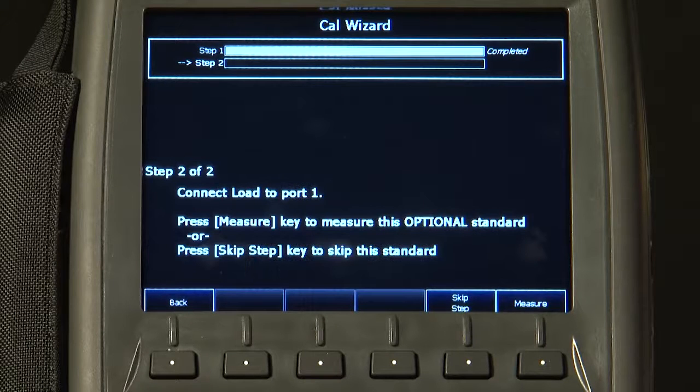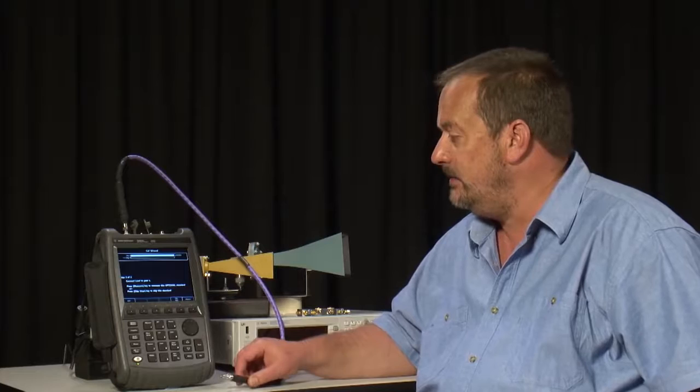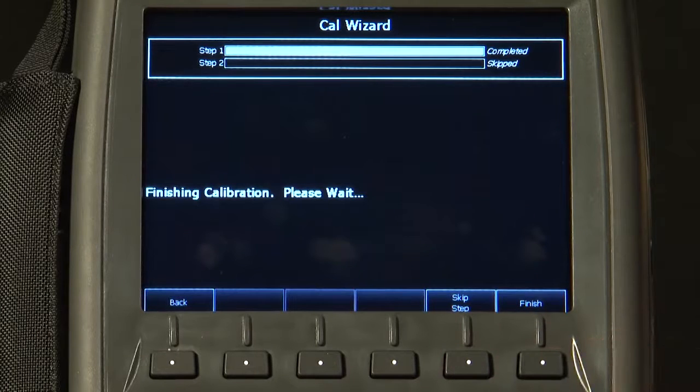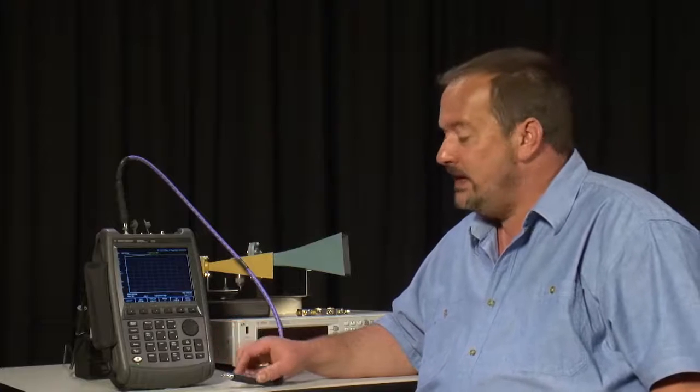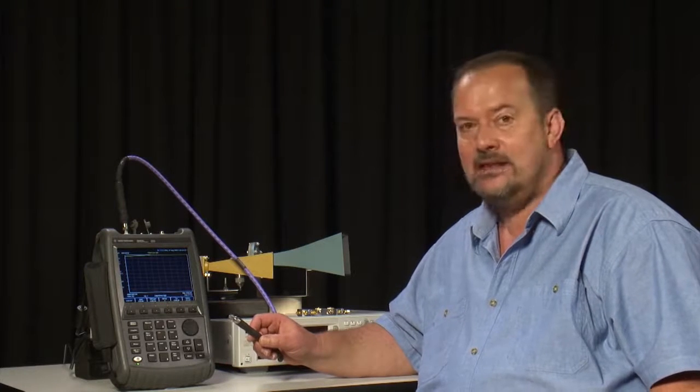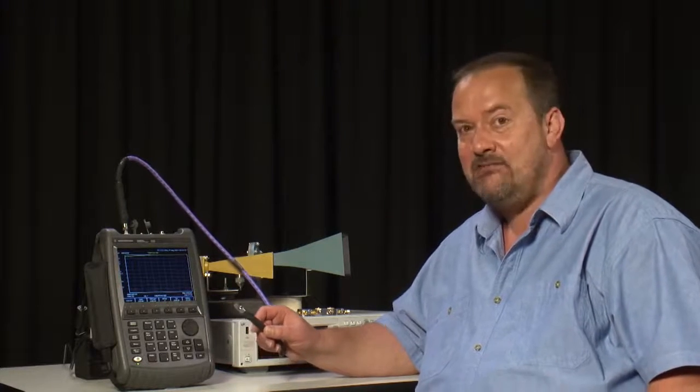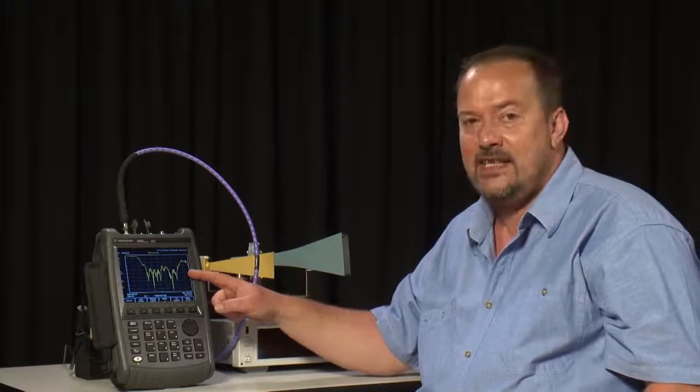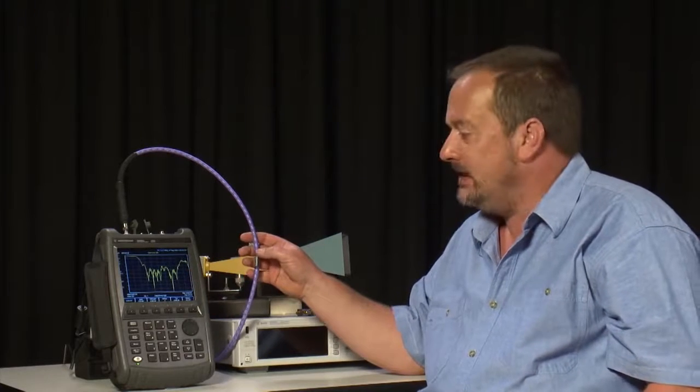And then it goes on to step 2, which is optional, which is to connect a 50 ohm load to the end of the cable. I will skip that step and press finish. And the FieldFox is now calibrated without using any mechanical calibration standards at all. I will now reconnect this to the antenna, and now we are measuring the return loss of the antenna without the effects of the test cable.